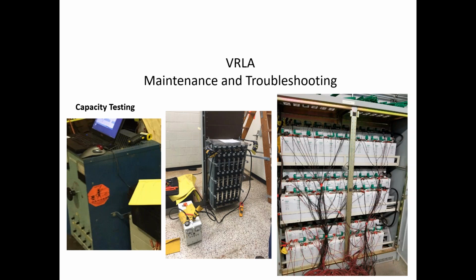This is just to show some of the system. We use Canon load banks, but depending on the amp hour, the size of the battery, we have larger units that roll in. And even this little guy here, I think he's rated at 400 amp hour. It's pretty amazing how compact some of the newer stuff is. And this is the master, but there are slave units you can parallel to it, and we're load testing a 48 volt system here. We have automatic data acquisition for larger cells.